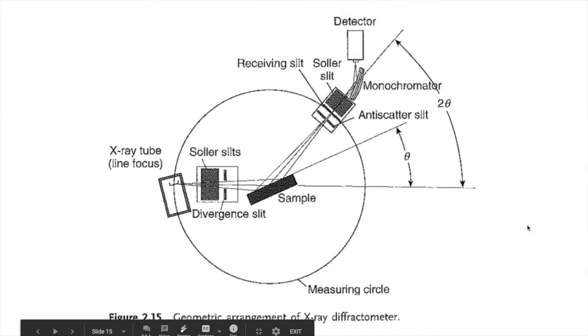So here's the geometric arrangement of a typical x-ray diffractometer using this Bragg-Brentano geometry. And so a couple things to kind of note about this is that the geometry requires that the diffracting planes of the sample should be parallel to the sample stage here. That way the configuration of theta, the angle, works out. So that also means that it should, the diffracting planes should be parallel to the sample surface. There are occasions where this may not occur but they should be parallel to the sample stage at the very least. Okay, so let's run through this arrangement and just kind of talk about the various components.